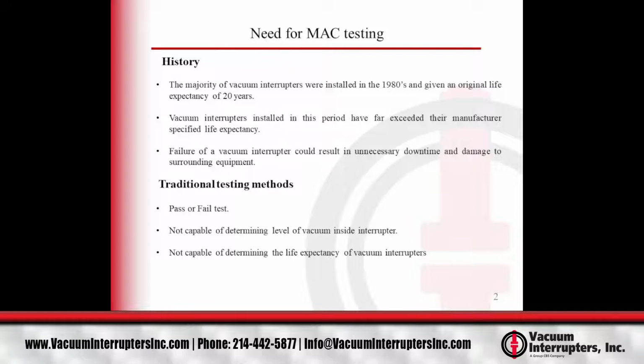So a little bit of history on vacuum interrupters. Many vacuum interrupters were installed in the mid-1980s, and many of those are still in service today. So they've well exceeded their 20-year shelf life that most manufacturers suggest. The standard test procedure is a high voltage or high pot test, where you increase the voltage to a predetermined set point, and if the vacuum interrupter is unable to insulate the voltage, then it's said to fail. Otherwise, it passes the test.